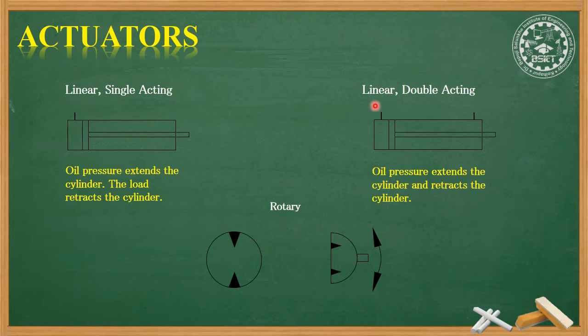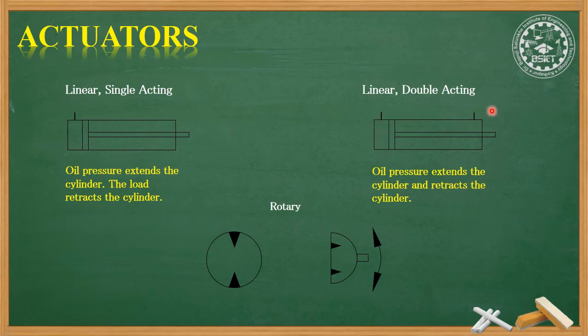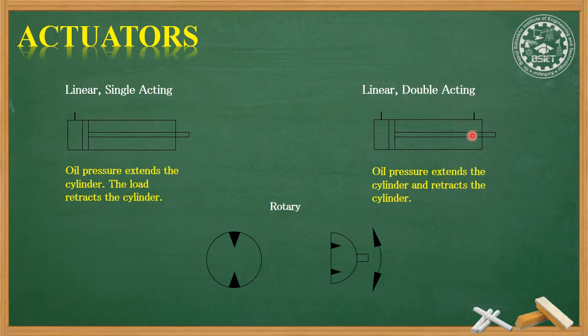Next is the linear double-acting actuator. Linear because the motion is in a line; double acting because you can see two lines on both sides, meaning oil entry happens from both sides. When we want to move the piston to the right, we send oil from one side so it moves forward. When we want to retract it, we send oil from the other side and the fluid pressure pushes the piston back to the left.